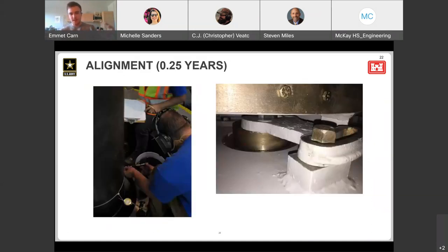Once the unit is back in place, that's when we do alignment. These hydropower units are really long—there's a turbine at the bottom, a long shaft, and a generator at the top. We want to make sure the entire unit is centered in the hole with no misalignment, because once you start a misaligned unit you can have a lot of issues with vibrations or other problems. So we do a lot of alignment checks to make sure everything is ready.